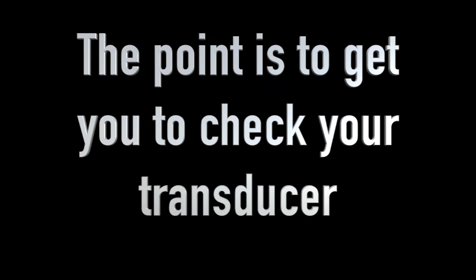Resetting the flag is simple. After you've reset the flag, we highly recommend that you take a good look at the offset to get a sense of whether or not the transducer may have been damaged.